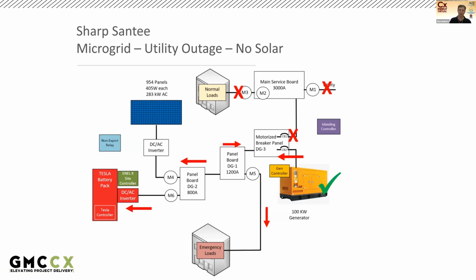And so the Tesla controller provides battery backup until it reaches 40%. Then it sends that signal to the generator controller to start the generator. The generator controller is paralleling and also grid forming. The controller modifies the engine governor speed until it gets to 60 Hertz. The generator controller then closes breaker CB2 once up to speed. CB1 is open, CB2 is closed, allowing the generator to provide power to the microgrid system. And then it runs. The generator provides that backup and charges the batteries while it's doing that. Another note is that the generator is also programmed to come on if, for whatever reason, the Tesla battery fails. That's another fail-safe: if the Tesla battery fails, the generator will automatically come on.